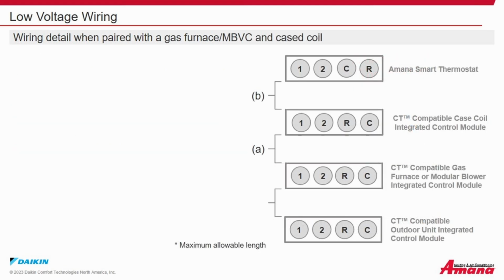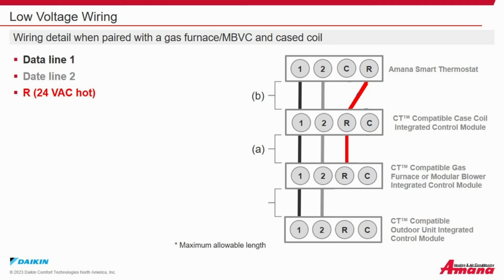Wiring detail when paired with a gas furnace or modular air handler and case coil. Data line 1, which should be 18 gauge stranded cable, runs from the Amana thermostat to the case coil, to the gas furnace or modular air handler, and then to the outdoor unit. Data line 2 also runs from the Amana thermostat to the case coil, to the furnace or air handler, and then to the outdoor unit. Also should be 18 gauge stranded wire. The R wire connects from R on the thermostat to R on the control module to R on the furnace. And the C or common wire connects from the thermostat to the case coil and to the furnace. Between the furnace and the thermostat should be a maximum of 125 feet. Between the furnace and the outdoor unit, communication lines can be 250 feet.